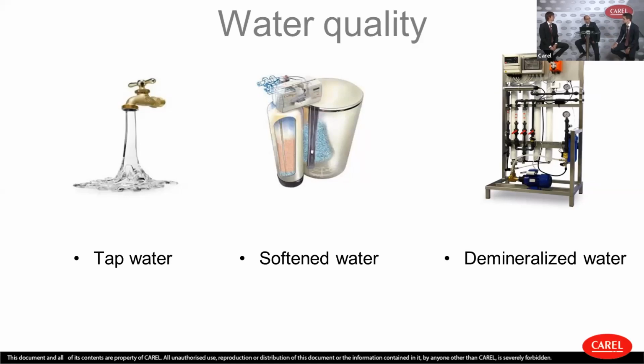The system works with all water types, but the problem is on the heat exchanger side. That's why I want to mention softened water: be very careful, because even though it has similar salt content, it can be even more aggressive than tap water, and corrosion becomes the main issue. Since you don't want to damage the heat exchanger, the most important part of the dry cooler, we don't recommend softened water.